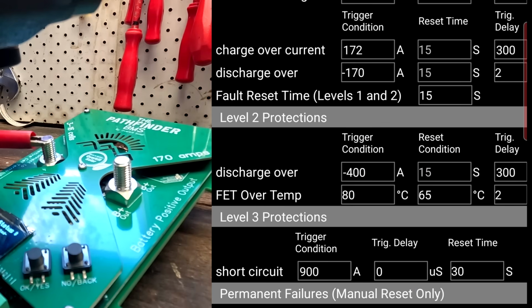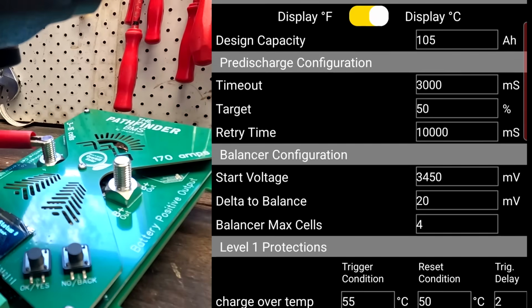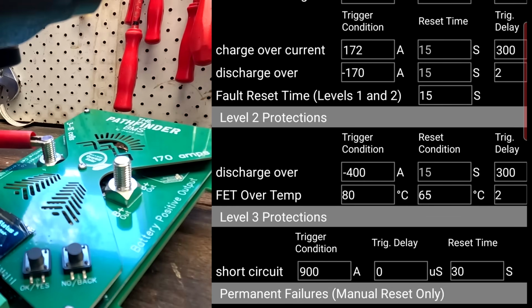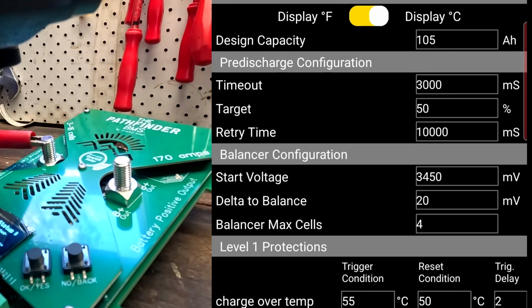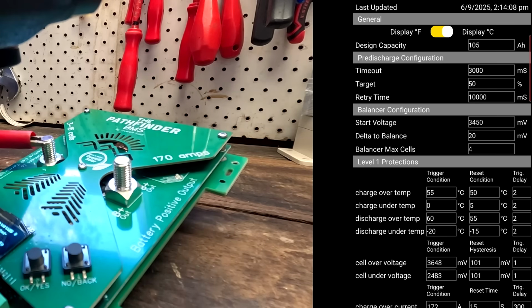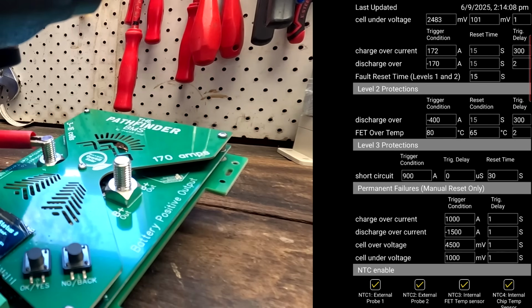So there are a lot of questions I have now, because these are not many parameters. These are the standard ones, but we cannot set any charge termination voltage, for example, where the BMS resets to 100%. This all seems to be hardwired, or I'm not on the latest firmware version, which I cannot update either because the Wi-Fi does not connect. All right, give me two minutes here. I have to do a bit of reading in the manual again and see how to set up the Wi-Fi, and then we have to determine if there's a newer firmware which actually allows us to change a bit more settings than only these basic ones here.